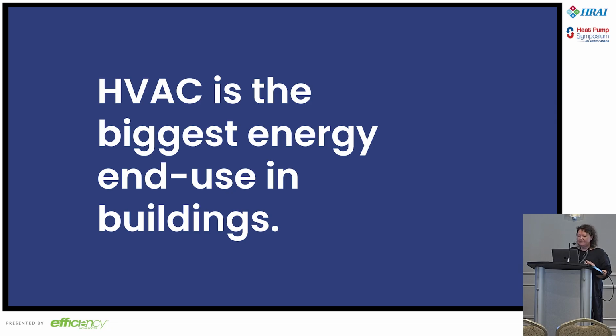And so in case it isn't obvious, we want every building to have a heat pump. But the issue, the dilemma, is that if we size the HVAC based on today's loads before the envelope is fixed, you're going to end up with oversized equipment when the owner eventually looks at upgrading the building envelope. In my experience most of them do eventually, sometimes with the same owner, sometimes when the building changes hands.